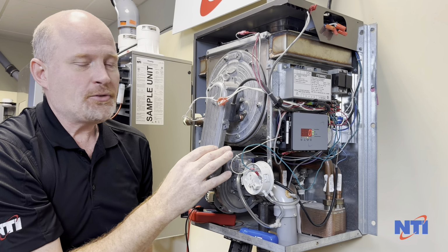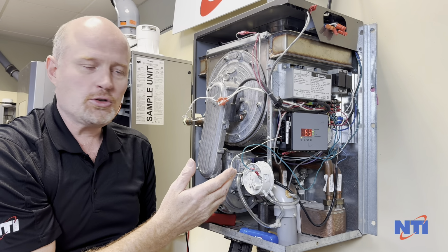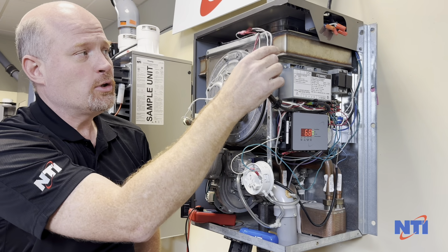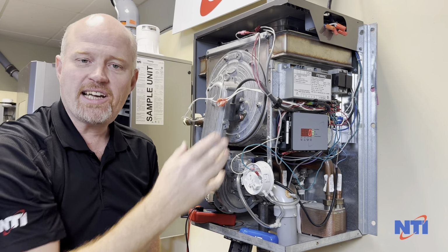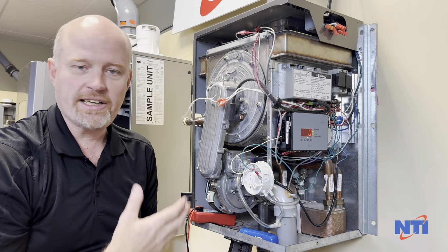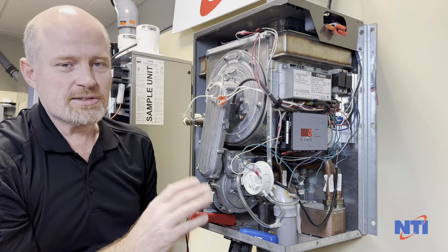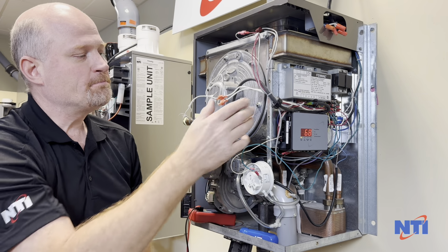This can happen if the thermostats have been replaced or the zone control's been modified. In some cases, and fairly rare, but could happen, if somebody zip tied some thermostat wires to a high voltage line in the house, like a stove maybe or something like this, that can induce a voltage in those wires. Fairly rare, but worth checking.